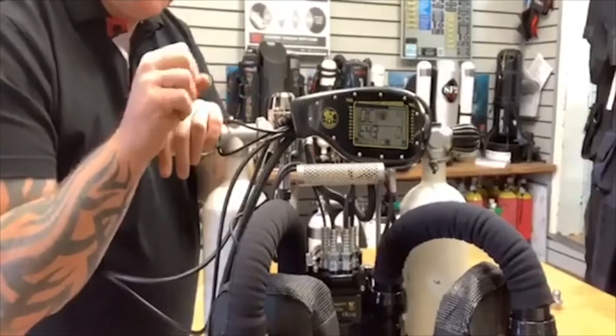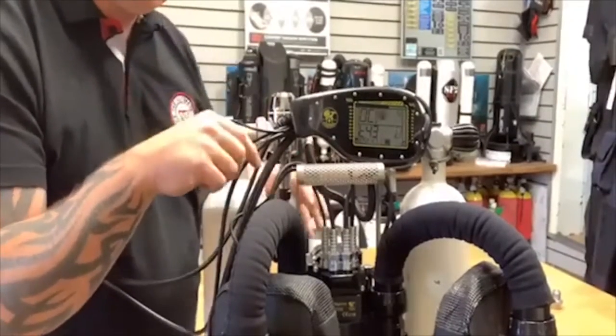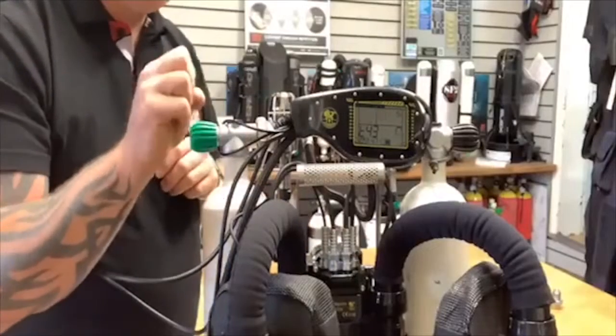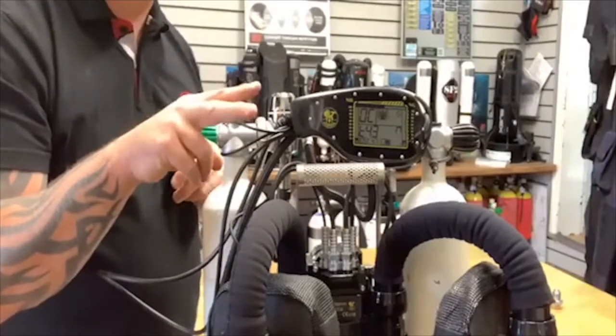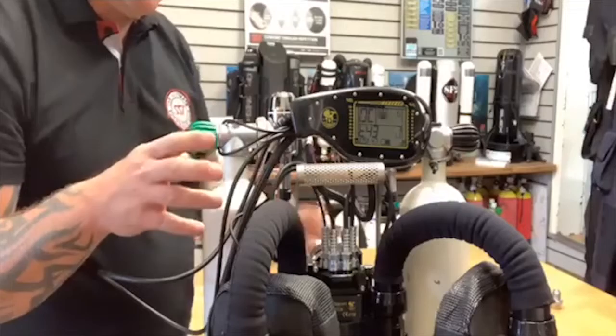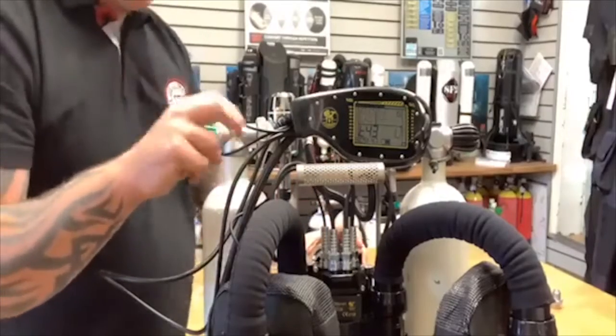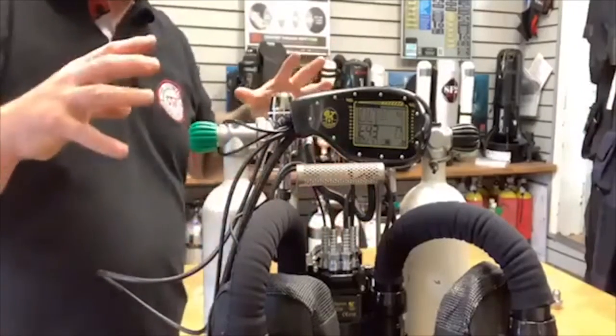If they then shut and the pressure does not rise, using a very sensitive sensor inside, it knows that those solenoids shut correctly and the solenoids are not in a stuck open position. That's an automatic feature. It'll then inject oxygen again to blow the rebreather to an even higher pressure and do our actual positive test.